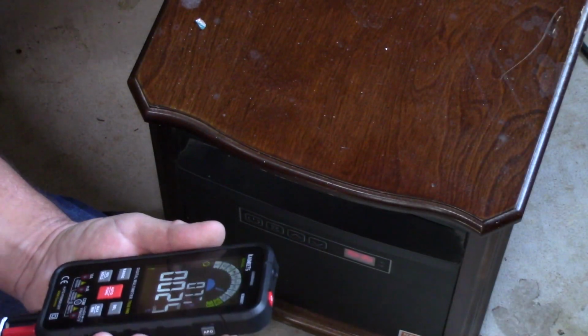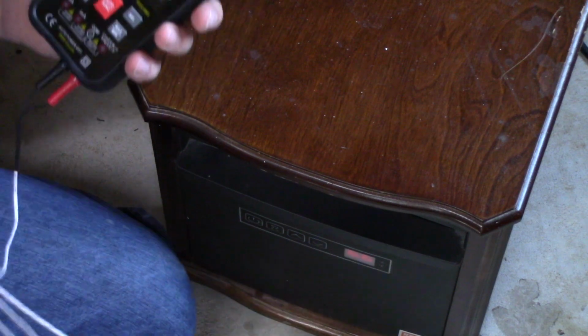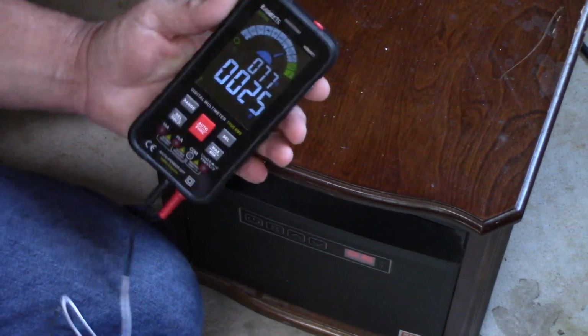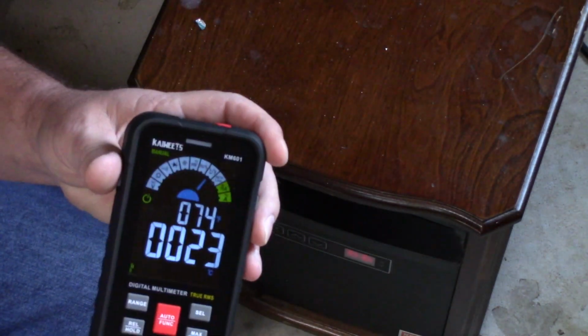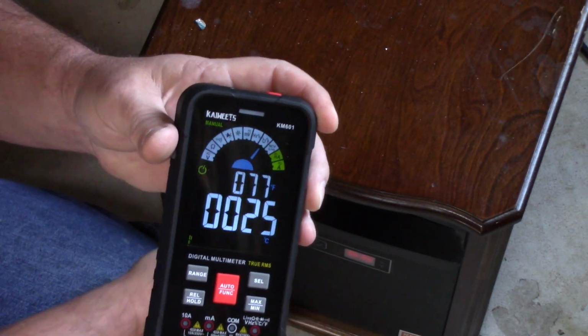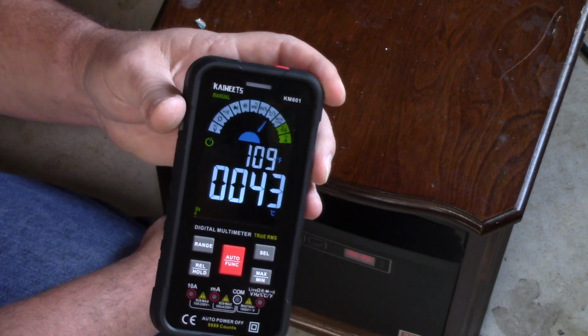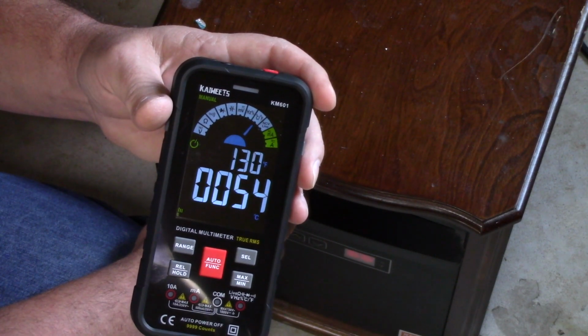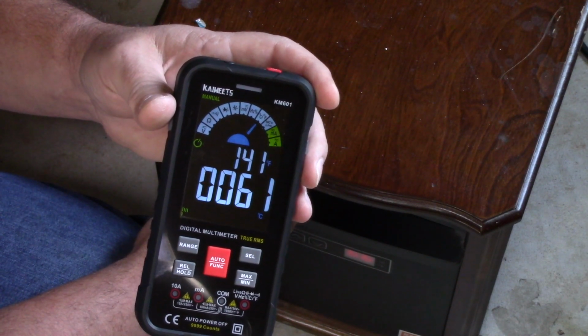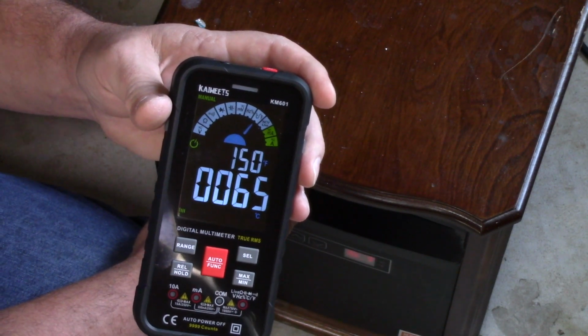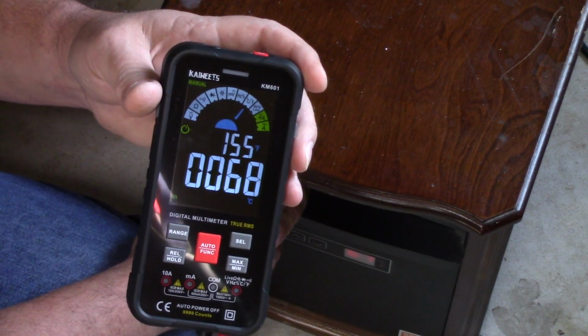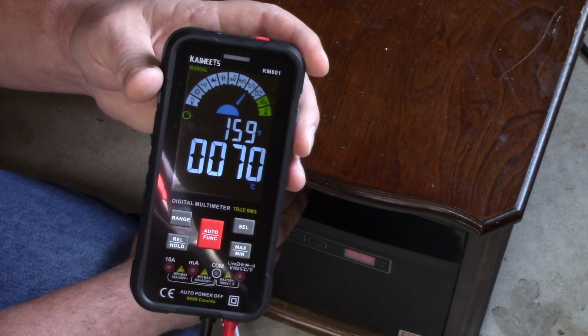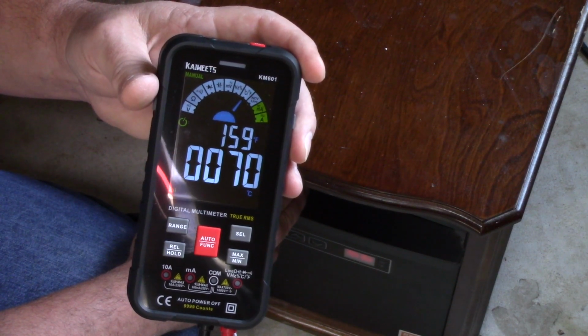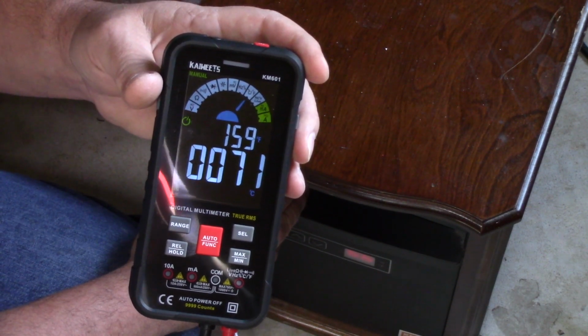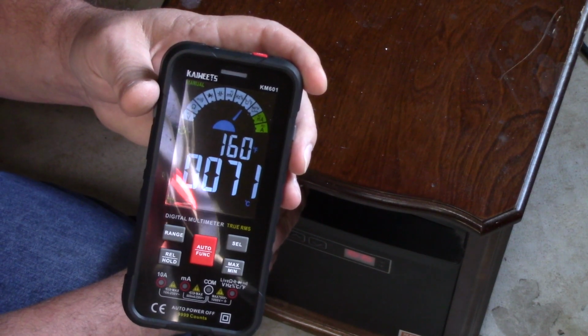I have it here in front of a little infrared heater running, just to test it. Hold the probe in front of the heater, and look at it climb, 127, 130, really climbing, not touching the metal grill, just holding it in front. My fingers are getting pretty hot. 159, probably climbing a bit more. That's pretty close to accurate - 159 degrees Fahrenheit, 71 degrees Celsius.